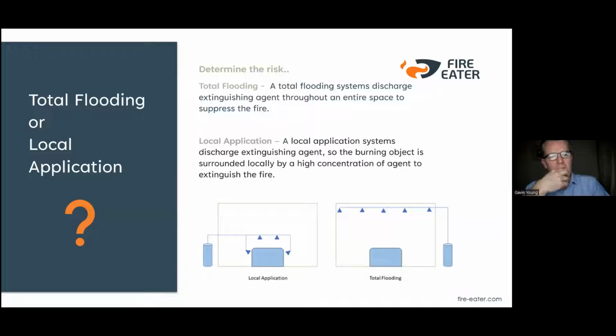So when you're looking at a fire suppression system, you've got a computer room or an archive store or something like that you want to protect with the system. So you've got to determine what it is you're protecting. So there's two types of system. There's a total flooding system, which discharges into the room and you need a sealed enclosure. And then there's a local application type, which discharges, as you can see at the bottom, to around, for example, a printing press.